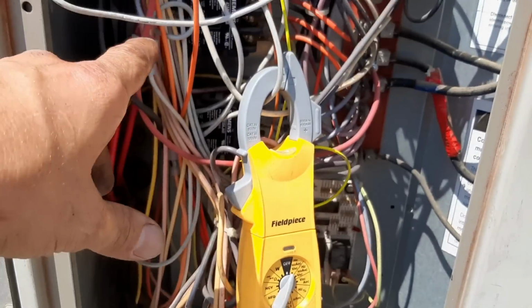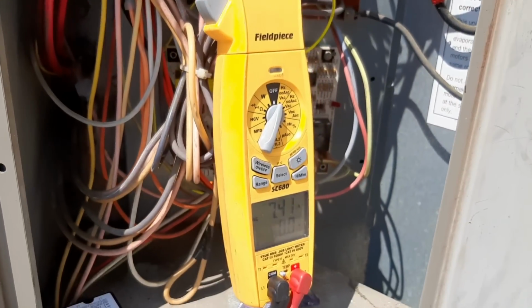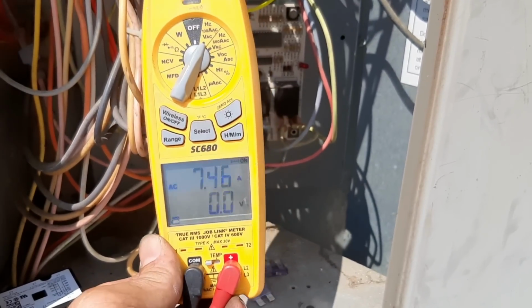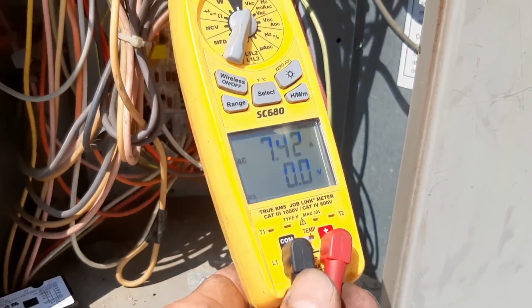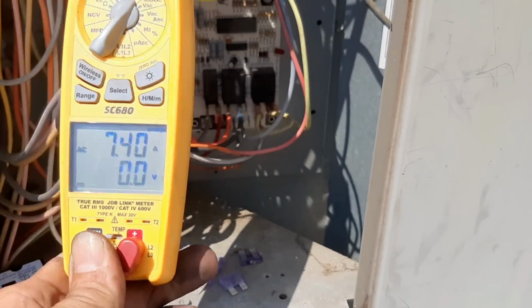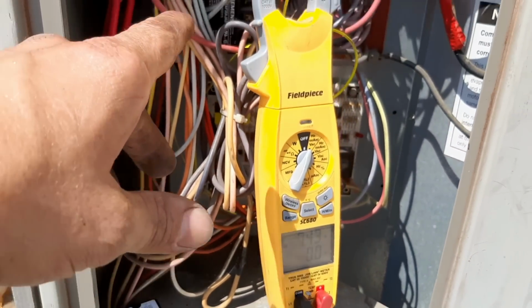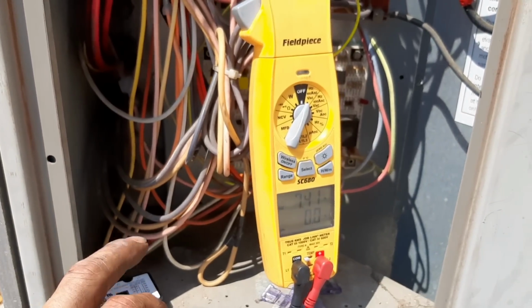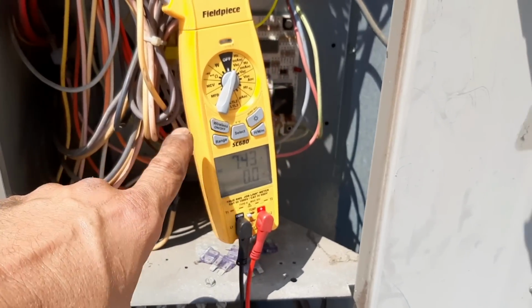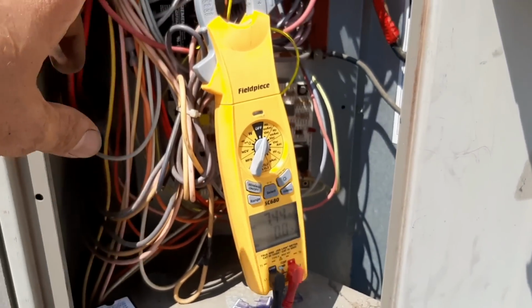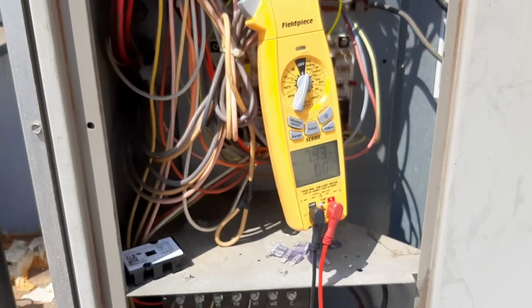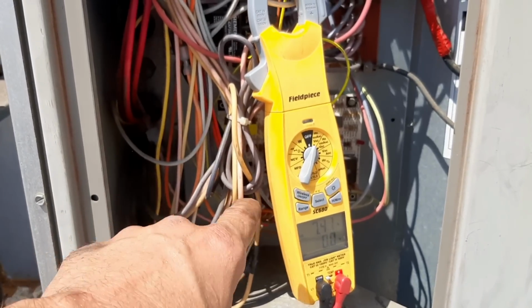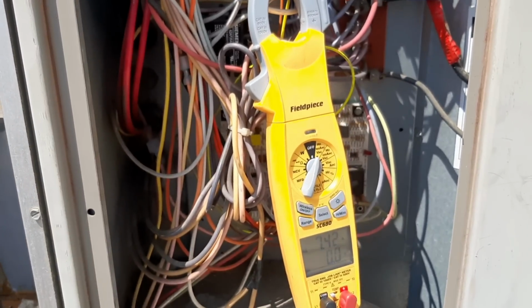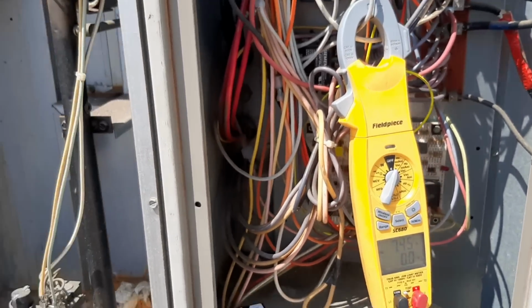I'm drawing 11 or 12 amps on both compressors. The blower's rated at 9.4 or something, so the blower should be alright. I still haven't figured it out, the second stage maybe was on a time delay from the board. I'm not exactly sure, because as soon as it came on, the blower came on too. So something's still not right with either the board time delays or how something's wired. But again, I'm not trying to make this perfect - it did come on by itself without me really doing anything to it.